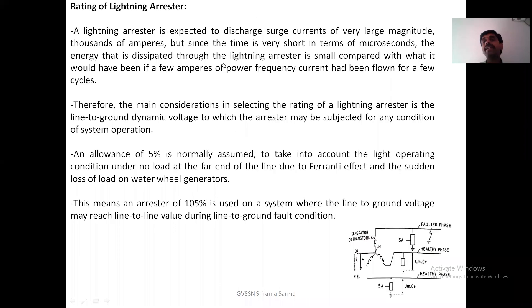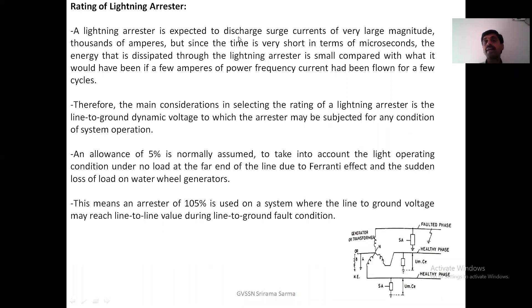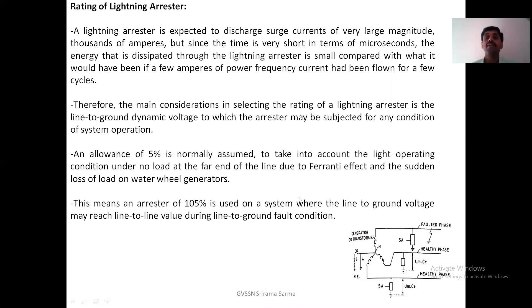What is the rating of the lightning arrester? The lightning arrester rating is expressed in terms of phase voltage — that means line-to-ground voltage. The lightning arrester is designed to discharge currents of very large magnitude. Why is the rating expressed in voltage and not in current? Normally they are expected to discharge large currents of thousands of amperes, but the time is very short — in microseconds they discharge the entire current.